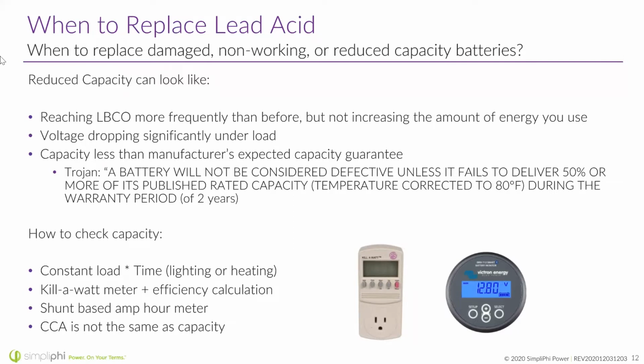This can also look like your voltage dropping significantly under a load. So if you turn on a large load and your voltage not only drops to 12.5 or 12, but all the way down to 11 or 10 volts, that is not normal. And your battery bank is likely having issues. That, or you have a loose connection in a wire somewhere.